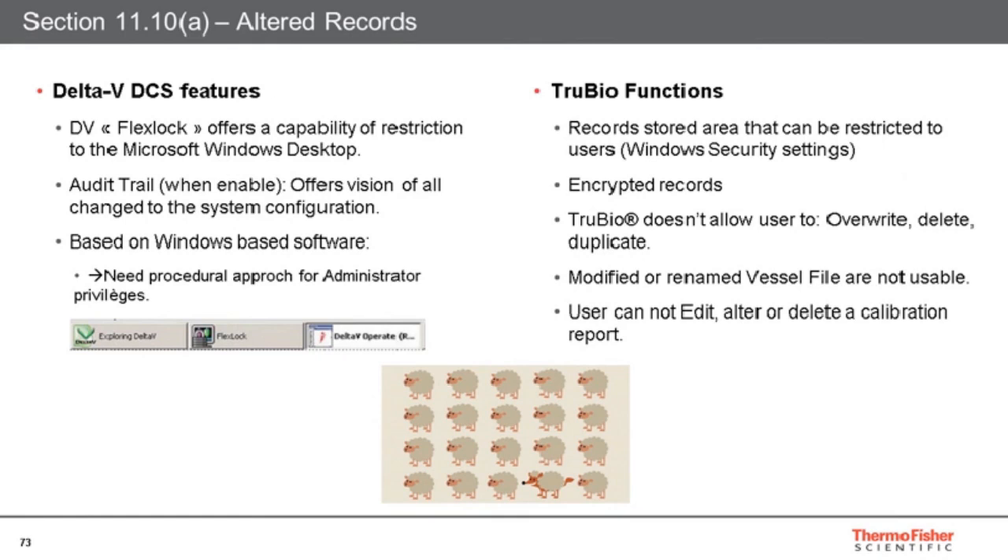Chapter 11.10(a) is about the risk of altered records, and it is managed mainly through different security levels. Records are encrypted, making any modification impossible. There is no possibility to overwrite, delete, or duplicate the data, and vessel files cannot be modified or renamed. The same concept is also applied for calibration reports. Of course, the audit trail offers visibility of any change to the system configuration. From a computer perspective, some procedural approach will be needed to define user accesses.